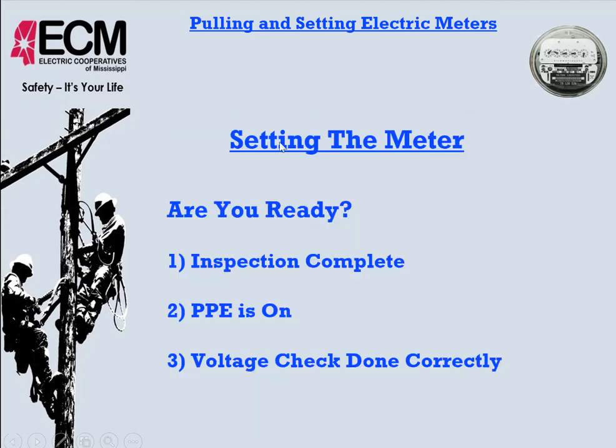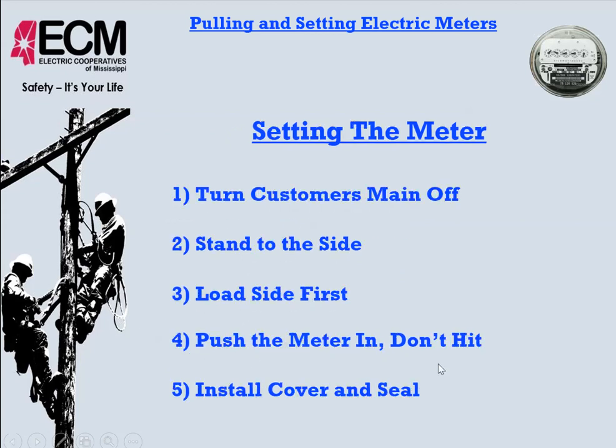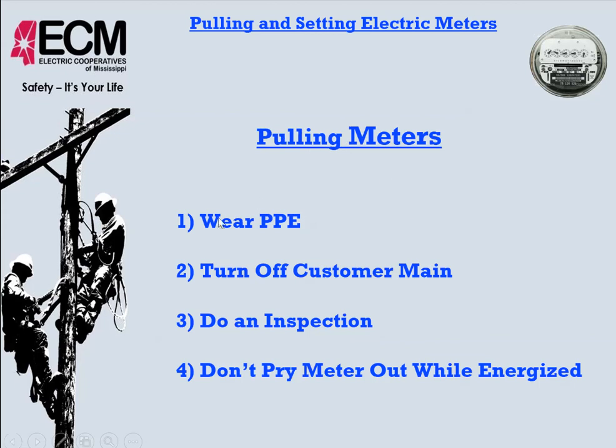And so, setting the meter, are you ready? The inspection's complete, PPE's on, voltage checks have been done correctly. You want to turn the customer's main off. Don't want to pick up any load with the meter. Stand to the side, set the load side first, push the meter in, don't hit, and install the cover and the seal. We've talked about that stuff extensively earlier in the program. So, pulling meters, wear your PPE, turn off the customer's main.